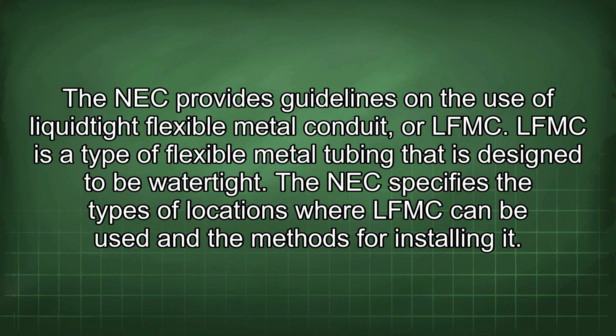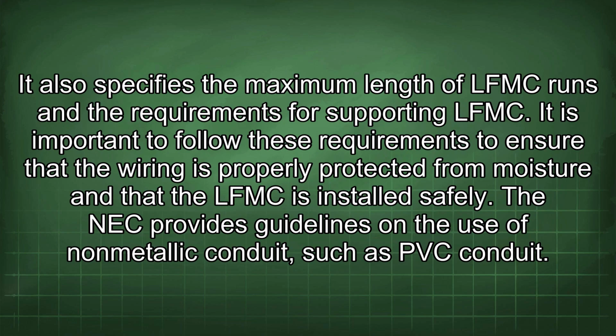The NEC provides guidelines on the use of liquid-tight flexible metal conduit, or LFMC. LFMC is a type of flexible metal tubing that is designed to be watertight. The NEC specifies the types of locations where LFMC can be used and the methods for installing it. It also specifies the maximum length of LFMC runs and the requirements for supporting LFMC.